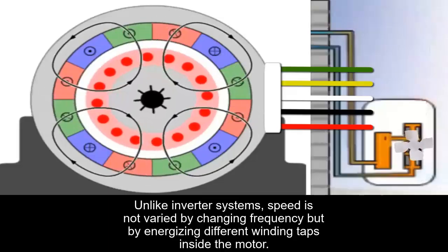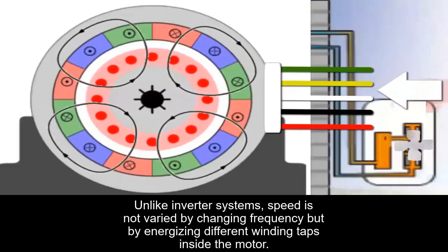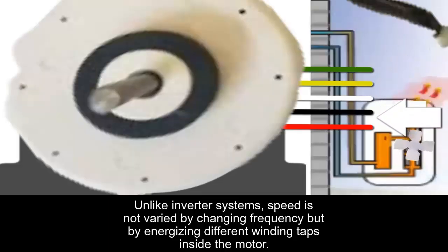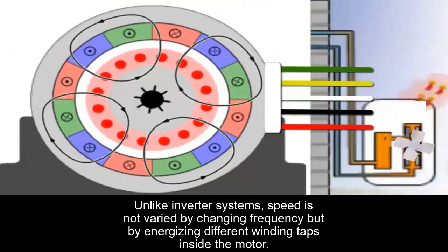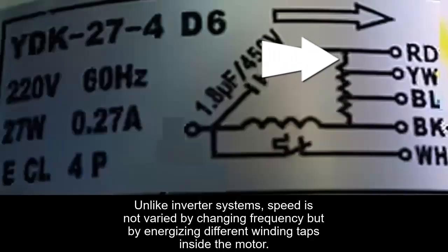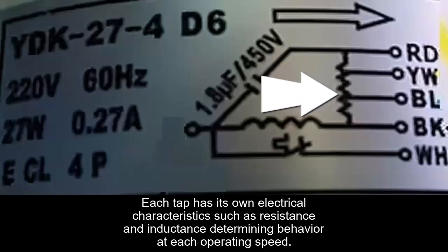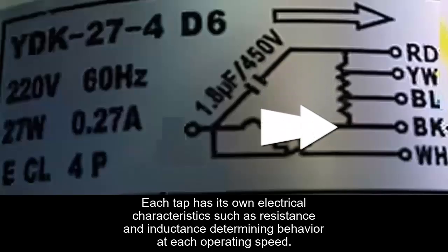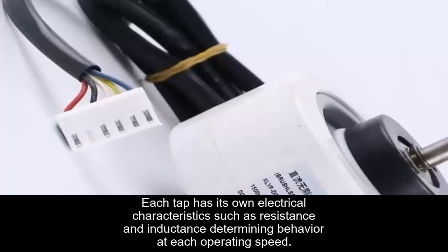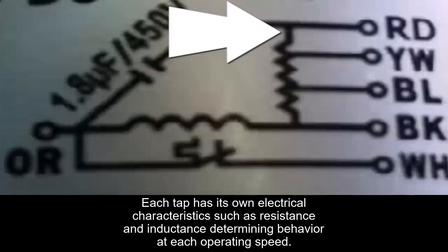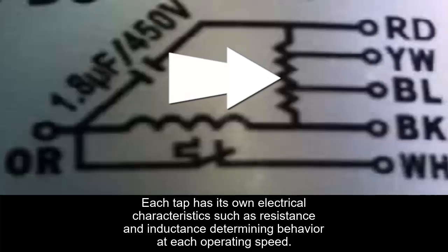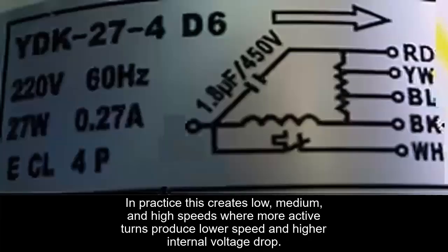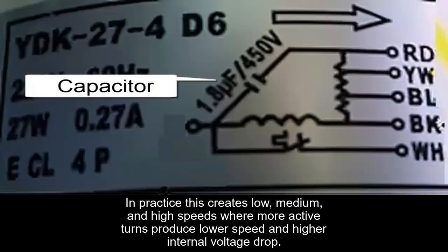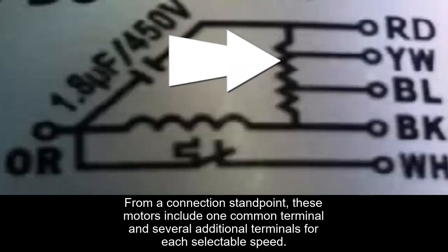Unlike modern systems with inverter technology, speed variation in these motors is not achieved by modifying the frequency, but by energizing different taps of the winding. Each tap has its own electrical characteristics, such as resistance and inductance, which determine the motor behavior at each speed. In practice, this translates into speeds such as low, medium, and high, where a greater number of active turns results in lower speed and a higher internal voltage drop in the winding.